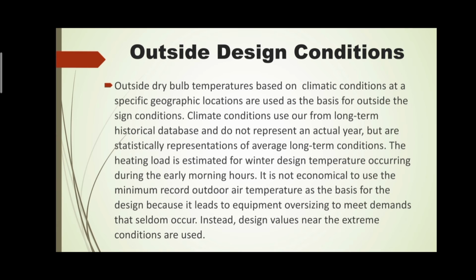Outside dry bulb temperature based on climatic condition at the specific geographic location are used as the basis for outside design condition. Yung outside dry bulb temperature, katulad ng pinakita ni Brisa kanina, it refers basically to the ambient air temperature. Climate conditions used are from a long-term historical database and do not represent an actual year, but are a statistical representation of average long-term condition. The heating load is estimated for winter design temperature occurring early in the morning hours. Yung heating load naman for winter ay nangyayari yan sa mga madaling araw na oras.